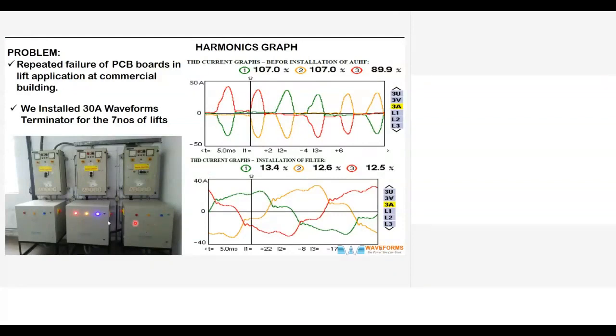So the harmonic level was as much as 107% in those drives at maximum. And the current is varying, in fact, it can be from just 1 ampere to a maximum of 12 amperes. It's a variable load, so the filtering also becomes a little difficult. But nevertheless, they reduced it substantially, more than 90%. And so it has improved the reliability of working, and we have reduced the harmonics.